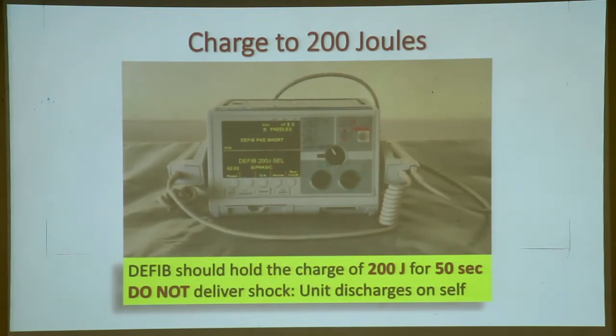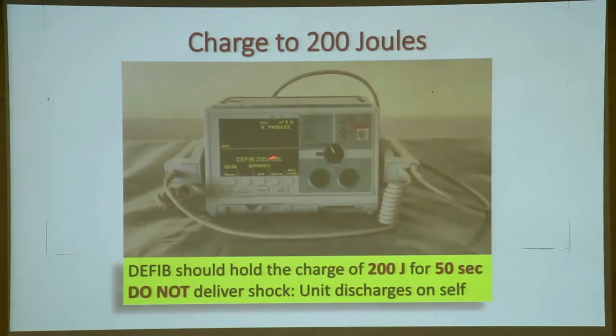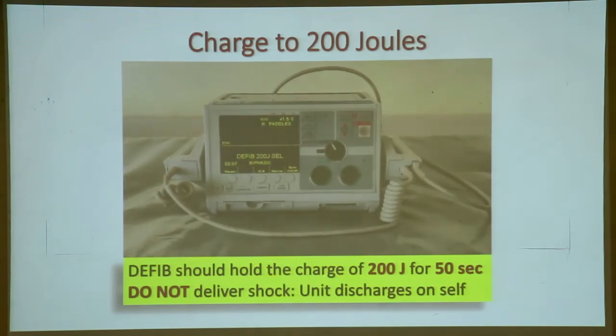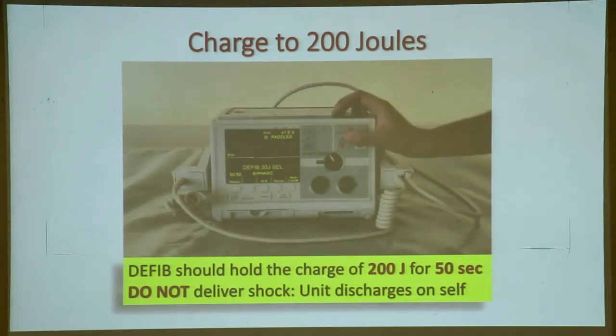Now it is gone. The ready, what was saying ready, it is gone, it says select. So the defibrillator has automatically discharged the amount of current which it was holding. You have not pressed the button. Right? So what it does is it doesn't deliver that charge to the machine components. It avoids the damage. At the same time, we know that it is charged to 200 joules and it is going to sustain that energy. I only need to discharge it by myself, or the machine is going to discharge it by itself. That's the weekly test which you must do. Okay. Am I clear? Okay.